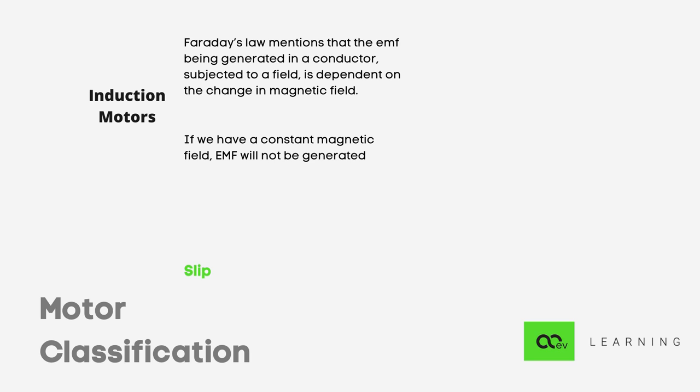If we have constant magnetic field, EMF will not be generated. In a hypothetical case of a motor's rotor running at a speed equal to that of the RMF, any particular section in the rotor will not experience any change in magnetic field as there is no relative motion. Thus, no EMF will be induced and no current will flow. No motion is possible. The rotor will not experience any torque. It will start to lag behind the speed of the RMF.